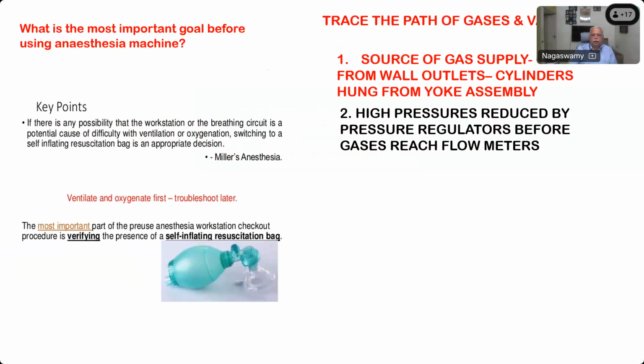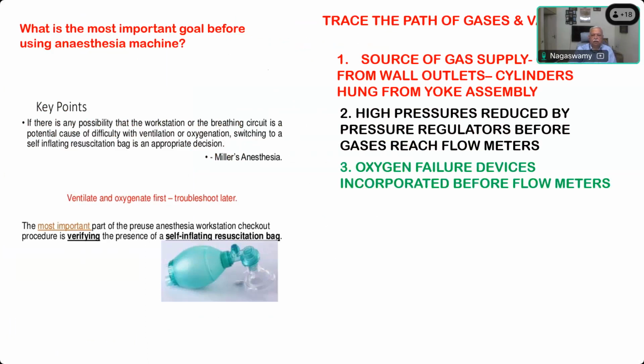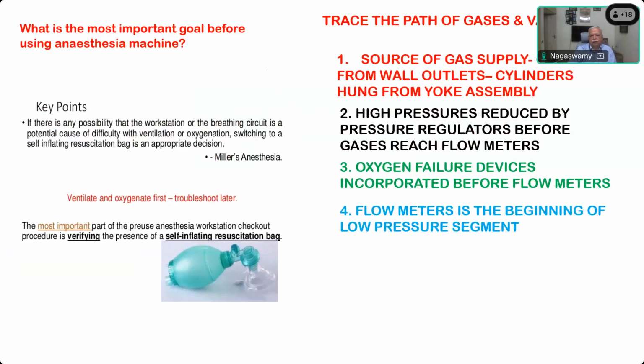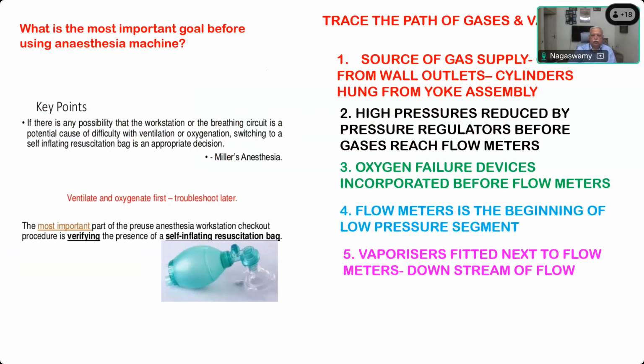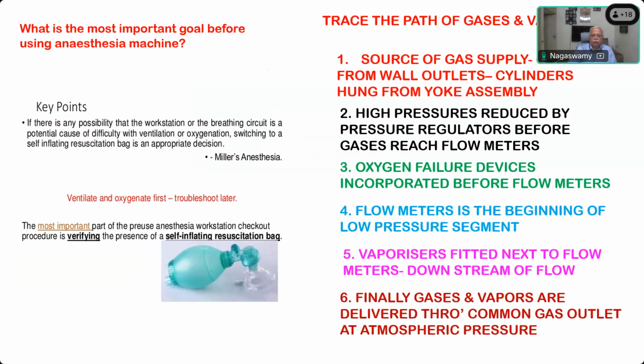Then check that the high pressure is reduced by the pressure regulator before gases reach the flow meters. That is the second stage. And oxygen failure devices are incorporated before the flow meters. And the flow meter is the beginning of the low pressure segment. Vaporizers are fitted next to the flow meters, downstream of the flow. And finally, gases and vapors are delivered through the common gas outlet at atmospheric pressure. Okay? So these are all the various stages or steps through which the gas has to flow.